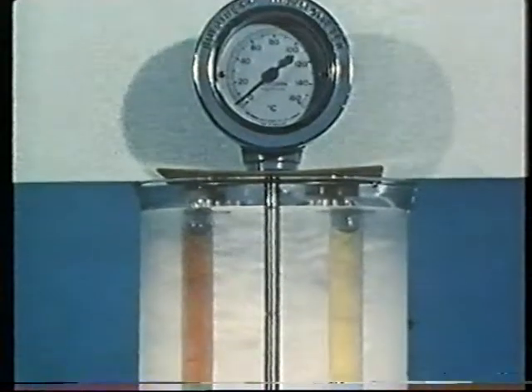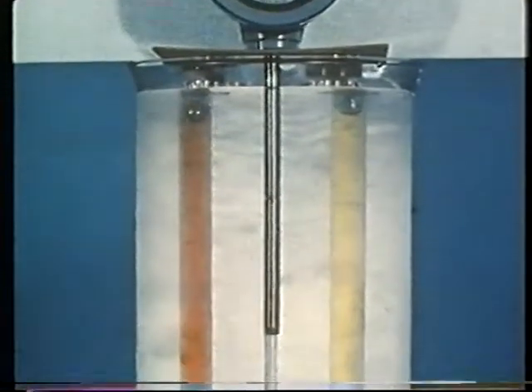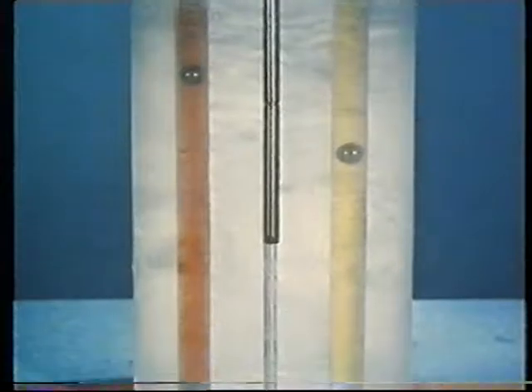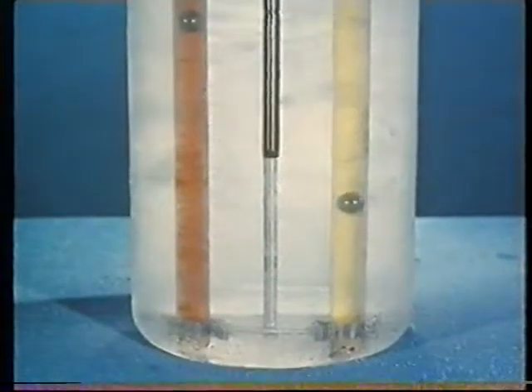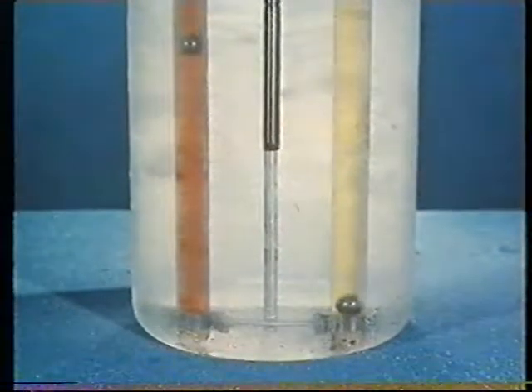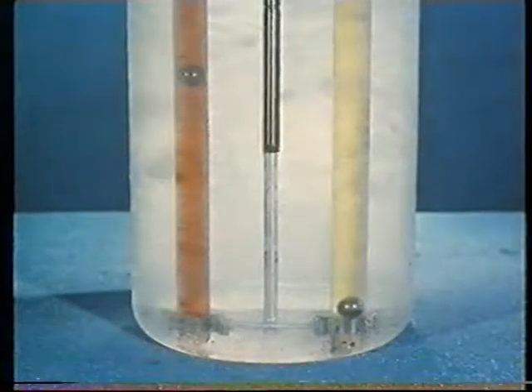Packed in ice, the left-hand sample thickens. Its viscosity has been affected by temperature change. The viscosity of the oil on the right has changed less, because it has a higher viscosity index.